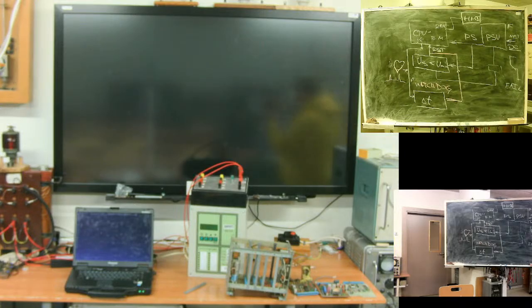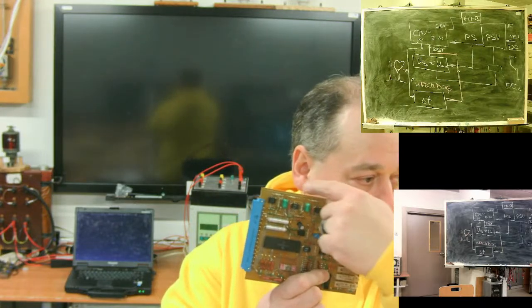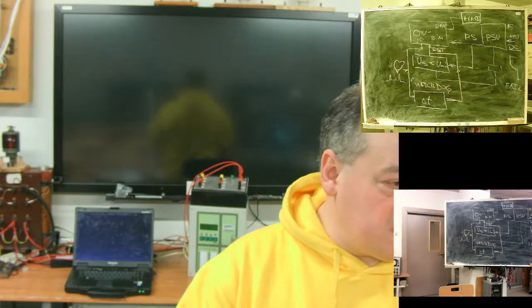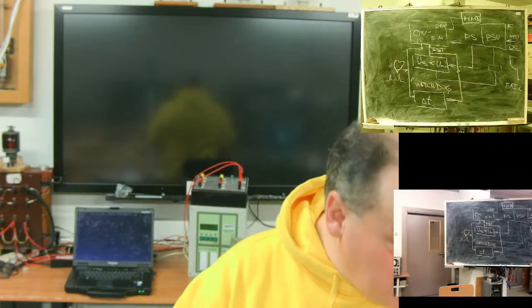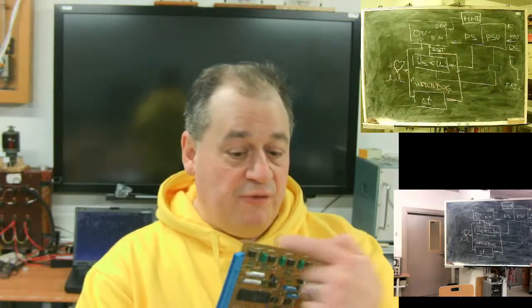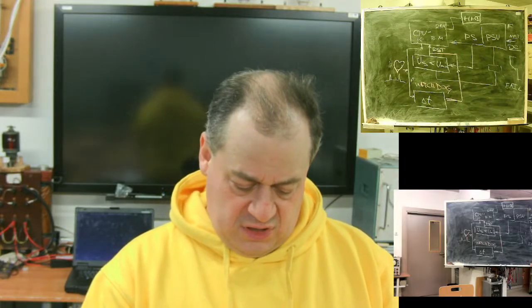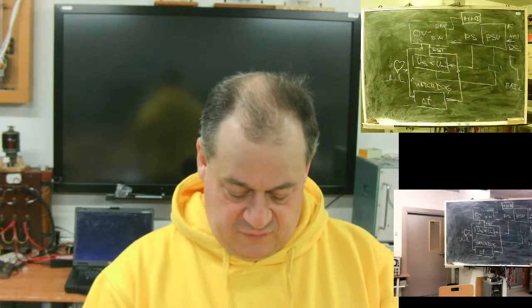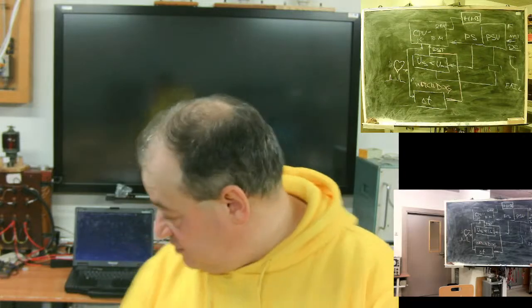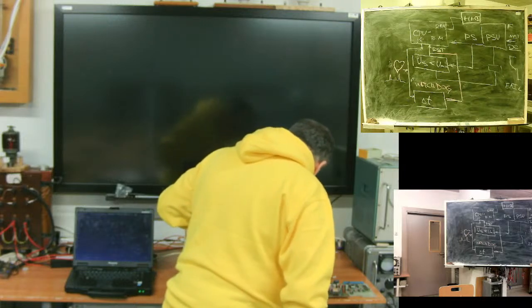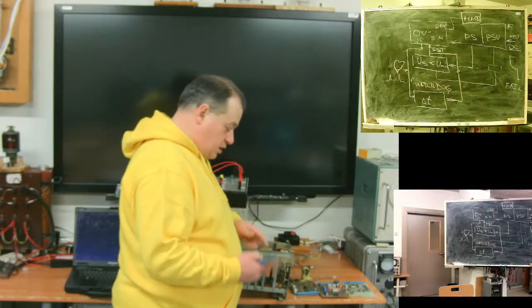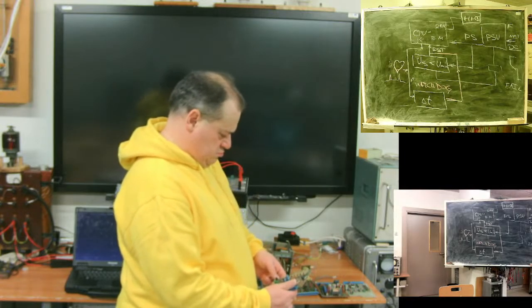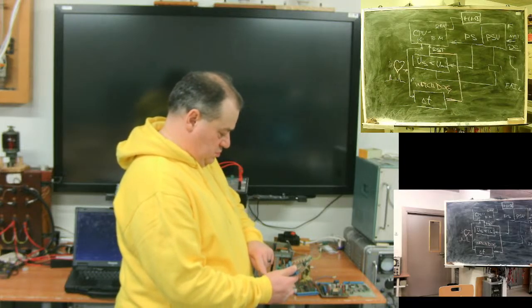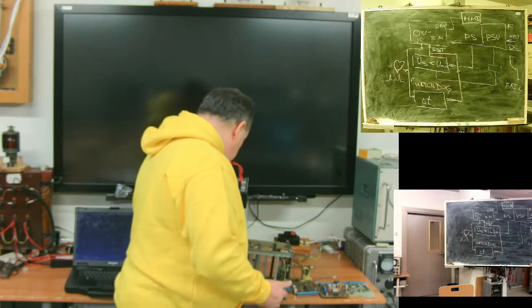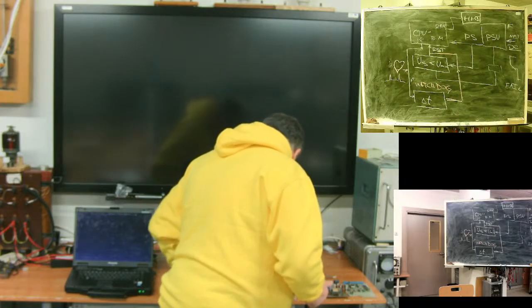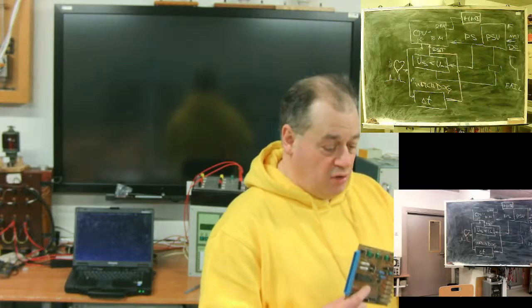Okay, coming back to this part. Operational amplifiers, capacitors, resistors. What is this? Analog filters. It's the analog preprocessing part of the device. Wait one second. 1, 2, 3, 4. The device should have 1, 2, 3 voltage channels and 1, 2, 3, 4 current channels. One, two, three, four. These are for currents and voltages. Analog filters, the analog preprocessing part.